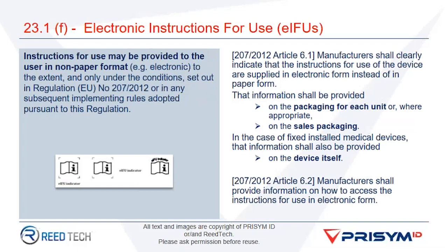To go even further, though, the IFU can now be provided electronically. The IFU regulations in the EU MDR have, in a way, been refreshing, but also at the same time frustrating. New regulations are moving in the direction that has been hailed by e-labelling enthusiasts, while still showing a degree of caution. IFUs are the only labelling element now that can be completely replaced with an electronic version. This needs to be clearly marked on the product label, and there's a new EIFU symbol, including the web location, that can be used to do that.